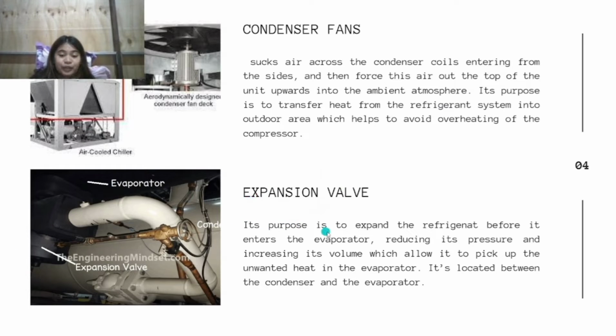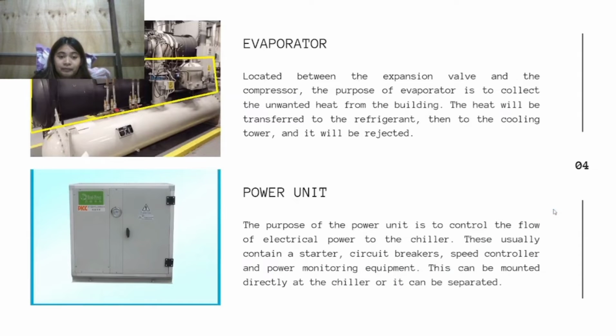Expansion valve. Its purpose is to expand the refrigerant before it enters the evaporator, reducing its pressure and increasing its volume, which allows it to pick up the unwanted heat in the evaporator. Evaporator. It is located between the expansion valve and the compressor. The purpose of this is to collect the unwanted heat from the building. The heat will be transferred to the refrigerant, then to the cooling tower, and it will be rejected.